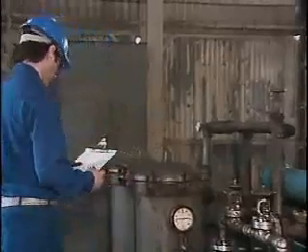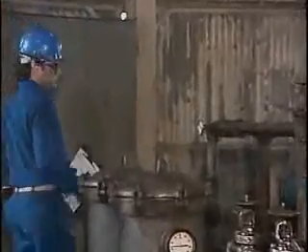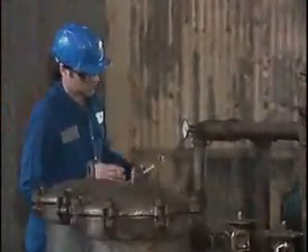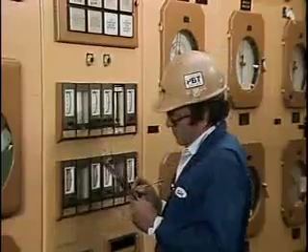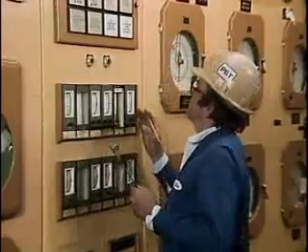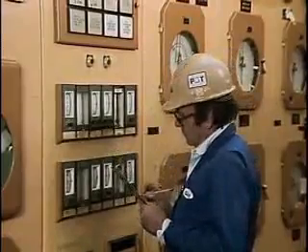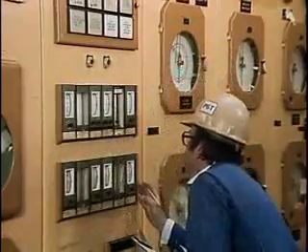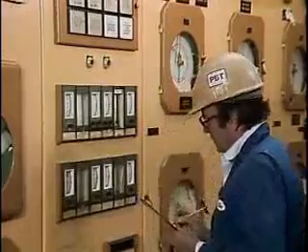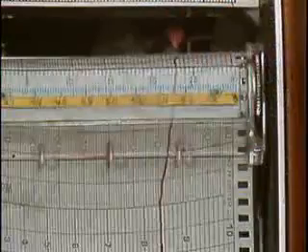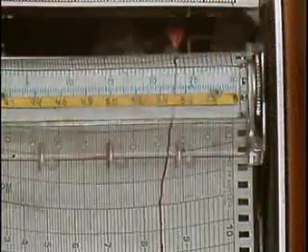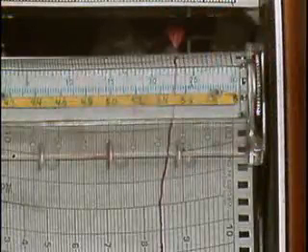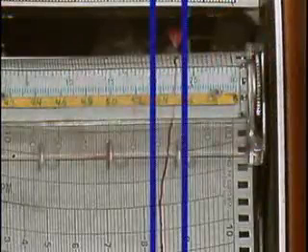Check the oil temperature too. If it's too high, there may be problems with the lube oil cooler. Other indicators can also help identify compressor problems, so they should be checked frequently. In many facilities, indicator readings are recorded on a log sheet on a routine basis. These records are important because they can be used to spot abnormal trends, which can indicate that a problem is starting to develop. For example, a steady increase in the compressor's cooling system temperature may be an indication of a problem.